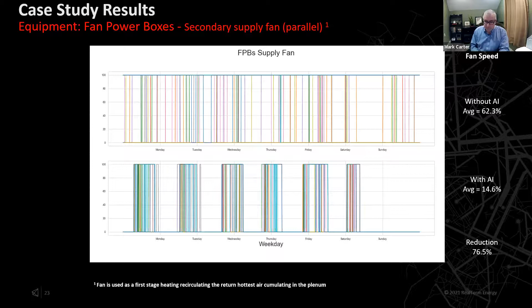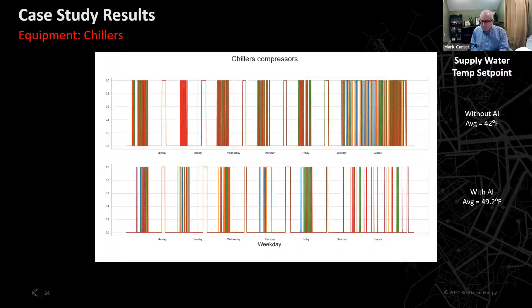So you had almost a 75%, three-quarter reduction in the utilization of the fan boxes. Next, chillers were comparable. In fact, with AI the water was actually a little bit warmer than without it, achieving those operating conditions with warmer chiller water, which also provides tremendous energy savings.